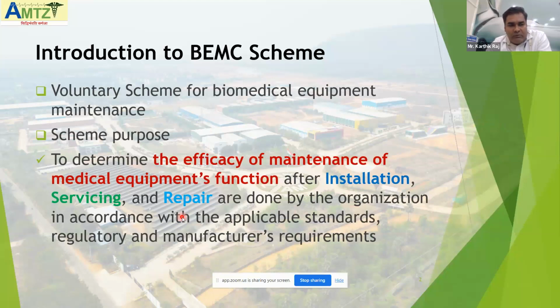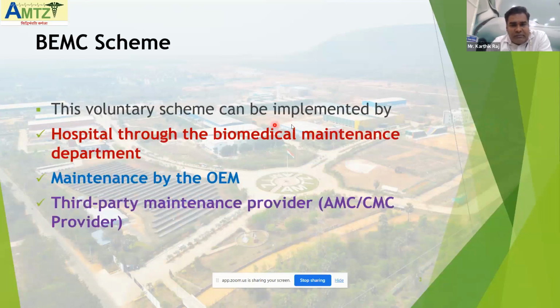And if you see in the global market, as per the WHO, 70 to 80 percent of the equipment is not in working condition. It either does not work, or it always has more downtime. In that case, the scheme will make sure that the equipment is in perfect condition and there will be fewer breakdowns, that is, less downtime. That is the main focus. If you implement this BEMC scheme, that will be the benefit for you. This is a voluntary scheme which can be implemented by the hospital through the biomedical equipment maintenance department.